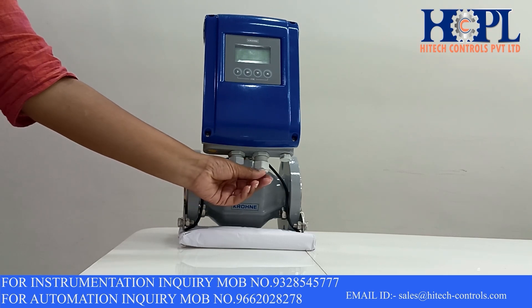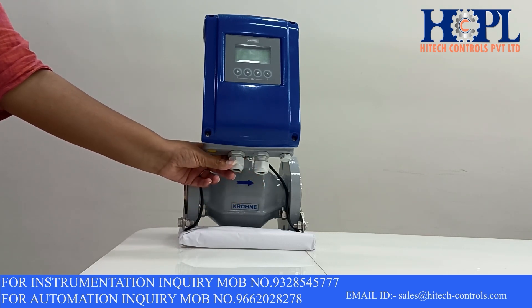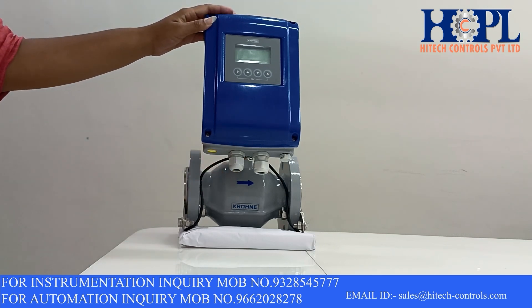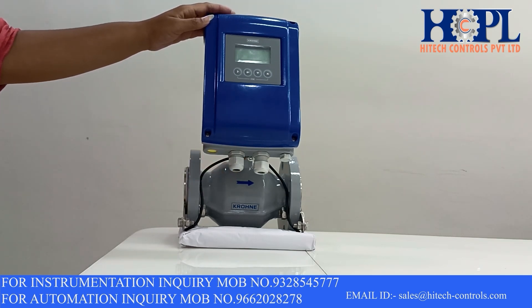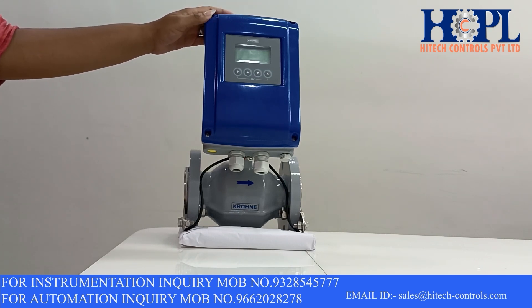You can give the electrical connection through these threaded parts. This transmitter is a 230V AC power device. You can also choose a 24V DC power supply for this transmitter. This transmitter gives you different outputs like 4-20mA current output with HART, pulse or frequency output and status output.